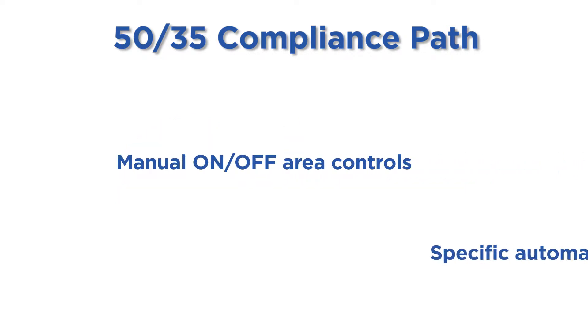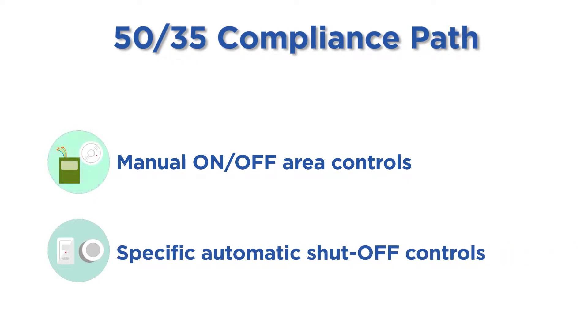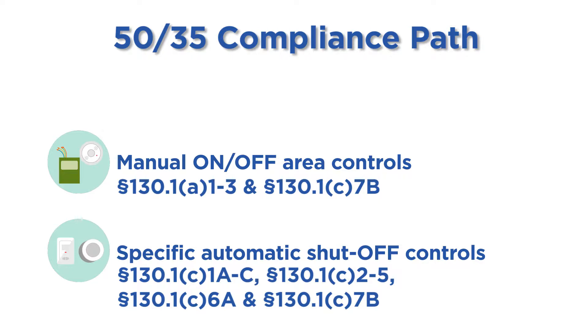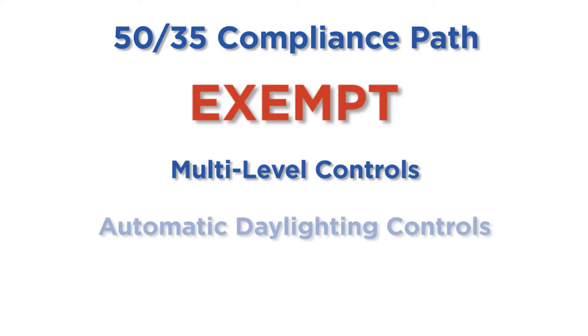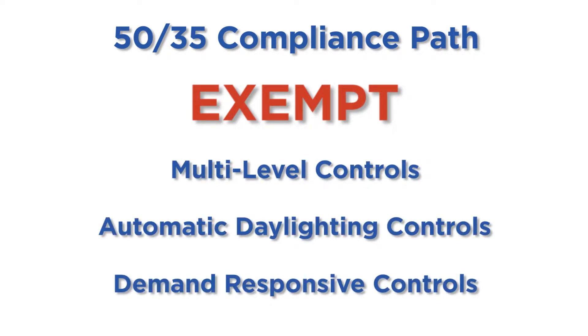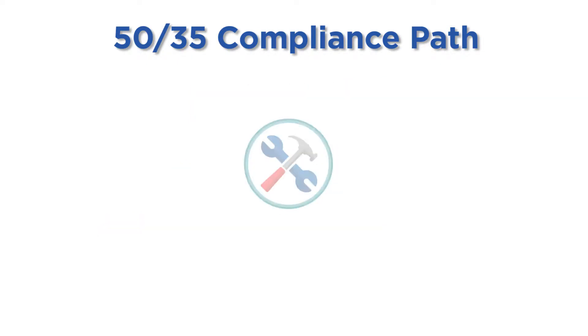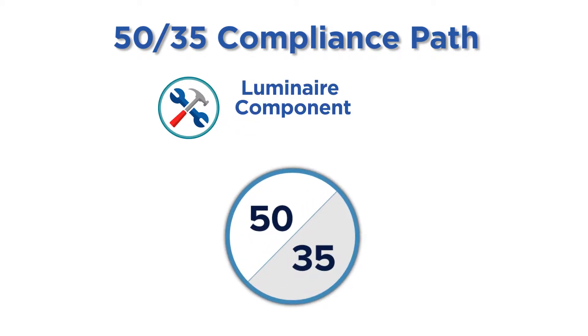If this criteria is satisfied, the only applicable control requirements pertain to manual on-off area controls and specific automatic shutoff controls. These projects are not subject to the multi-level, daylighting, and demand response control requirements because the power of the luminaires is being reduced substantially. Projects involving luminaire component modifications may also opt to comply via the 50%-35% power reduction compliance pathway.